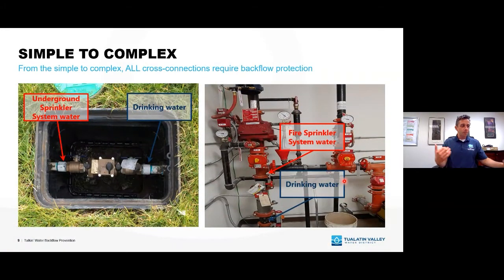Because backflow can at times be unavoidable, the way to protect drinking water within your plumbing system and the distribution system is proper installation and maintenance of backflow preventers. Backflow preventers are required at connections within a plumbing system where potable piping connects to a non-potable fixture or non-potable piping - also known as the point of these cross connections.